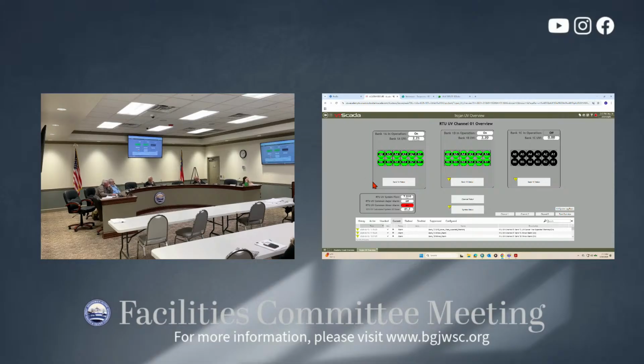So we can tell which of the individual light bulbs are burning on each of the 9 banks of bulbs that we have. If one of them goes out, now there are 12 bulbs per bank, and it will actually read individual pin connectors that tell you which ones are running and which ones are not. It will tell you the current dosing rate of the UV, basically the power consumption of those bulbs, to tell you what the brightness is. Obviously, these are turned down low when there's low flow so that we don't waste as much power.